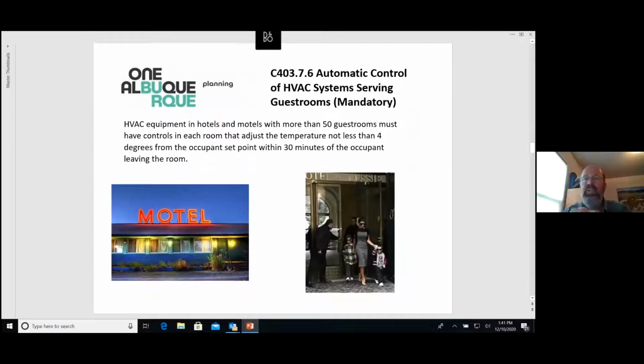Automatic controls serving guest rooms. The equipment in hotels or motels with more than 50 guest rooms is required to have controls that adjust the temperature not less than 4 degrees within 30 minutes of an occupant leaving the room from the occupant set point. So they're talking about key cards to sense when you come and go, probably other sensors to address when the system should roll it back.